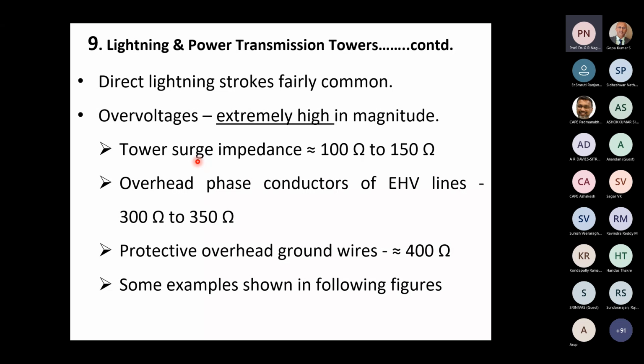Typically, the value for large towers is 100 to 150 ohms. The largest towers have an equivalent surge impedance of 100 ohms. The surge impedance is given by root of L by C, where L is the inductance per unit length and C is the capacitance per unit length of these towers with respect to ground, inductance of course with respect to the magnetic field only. Therefore, the surge impedance has very substantial values, 100 to 150 ohms. The larger towers have 100 ohms, medium towers have 150 ohms.